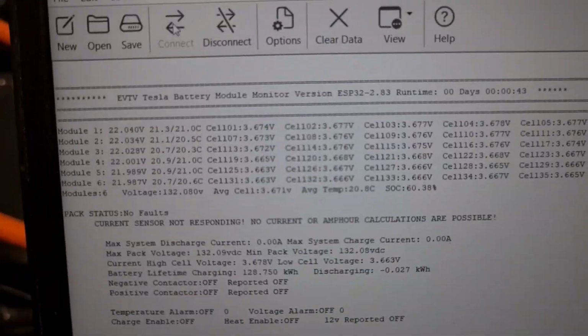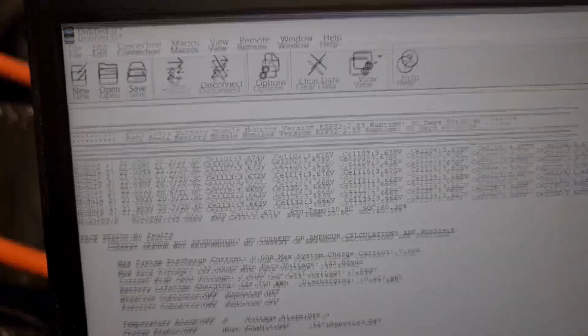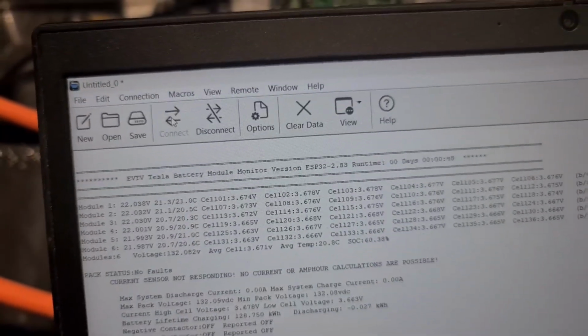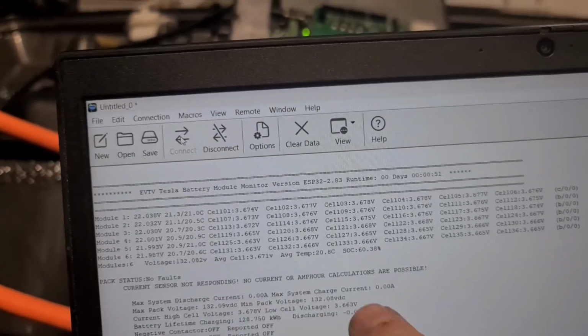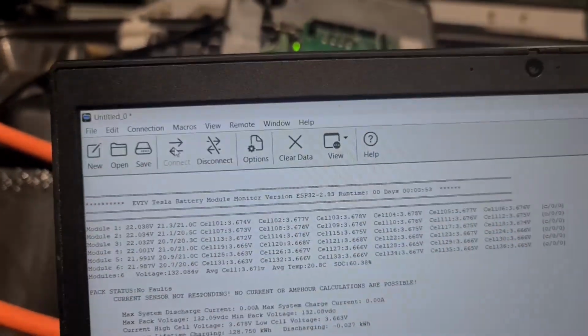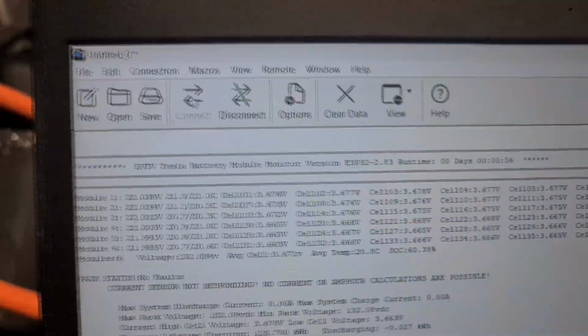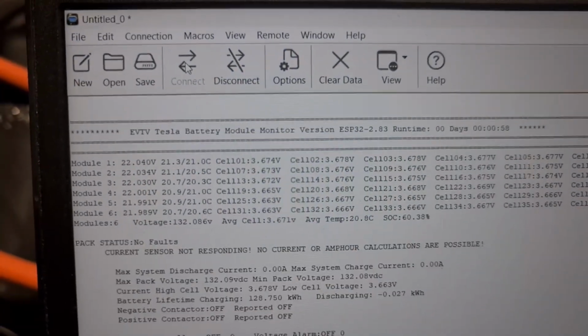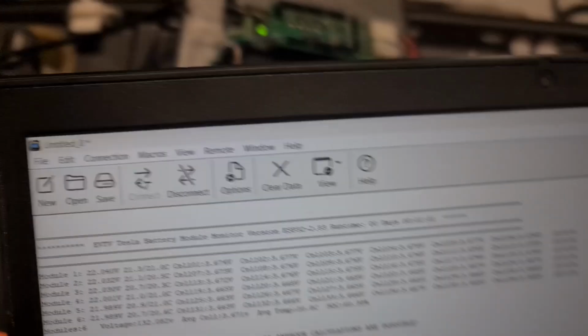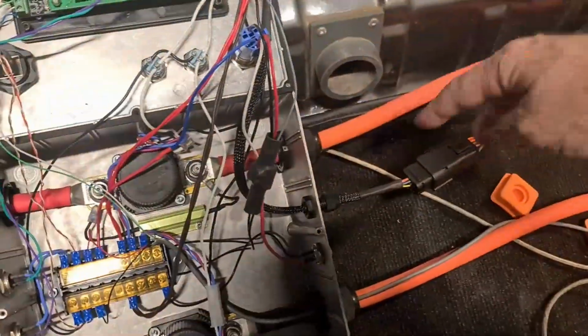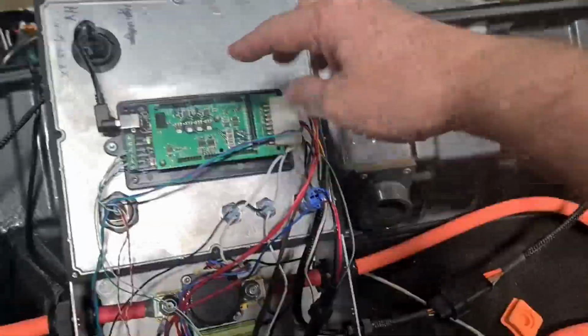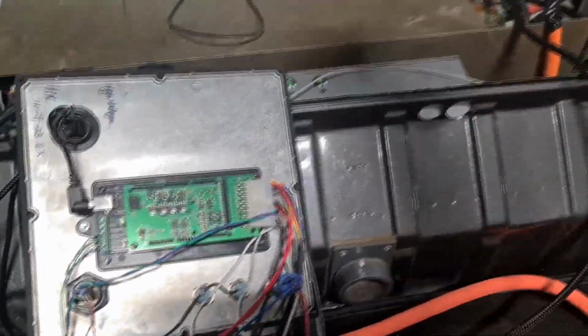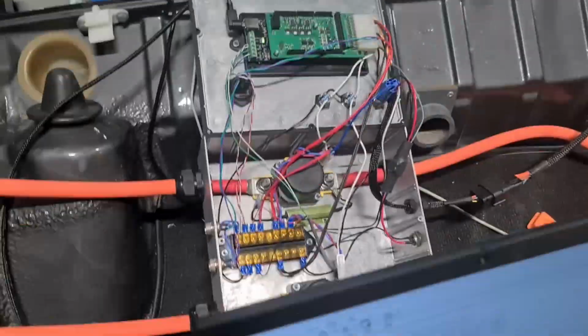I plugged the cable into this one, and look, we have 6 modules. We have 132.086 volts. The current sensor isn't the one I care about. We have data, communications. So this tells me there's a difference between the wiring in this box that works and my box that doesn't, and that's a dead simple thing to fix.